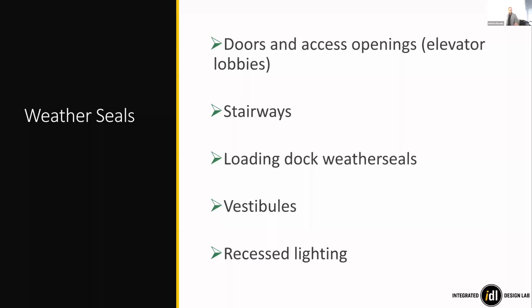Other requirements for sealing up the building: if you've got a room with a fuel burning appliance—your boiler, your water heater that's gas—either you can have it just outside your building envelope, that's great, or there's a whole bunch of prescriptive methods for what to do if it's within your building envelope, making sure it's sealed and insulated in certain ways in terms of gaskets around the dampers, insulation, at least meeting the below ground requirements in the 2018 IECC. It's a little bit different than the rest of the space.